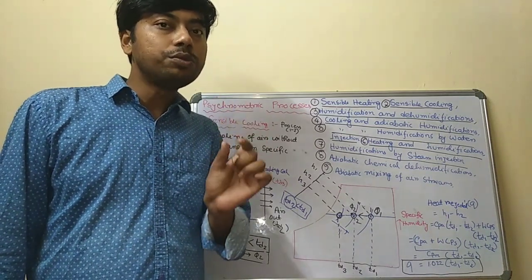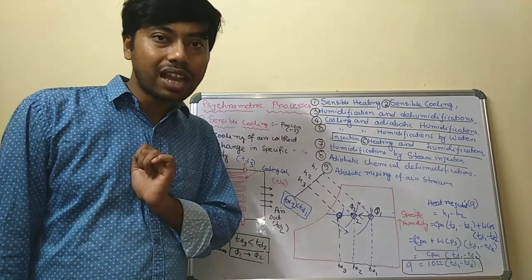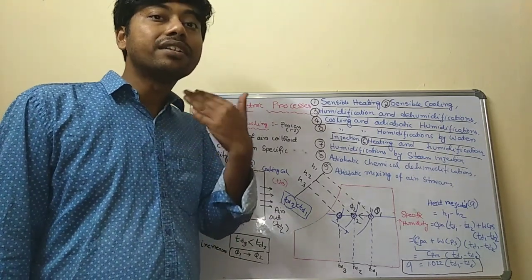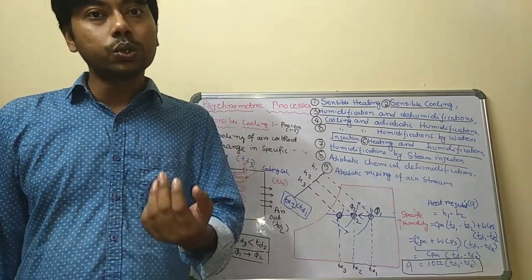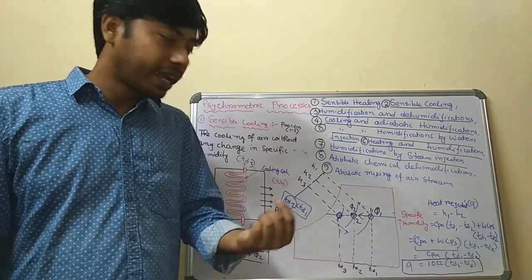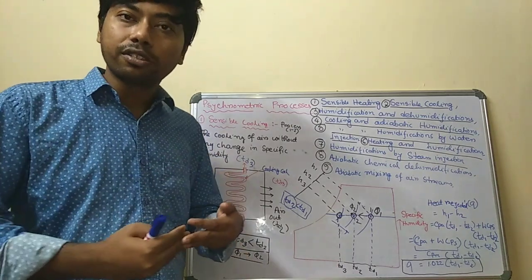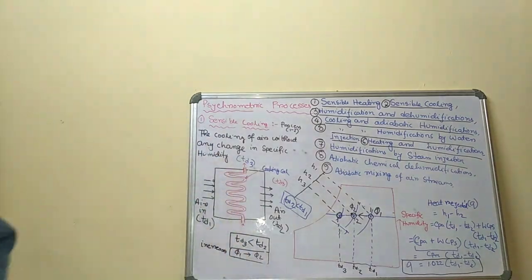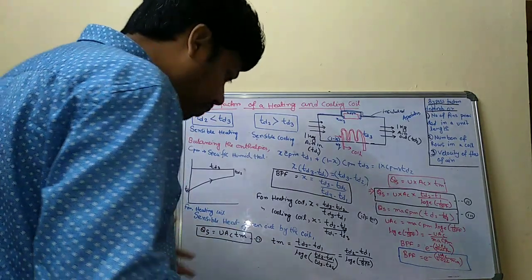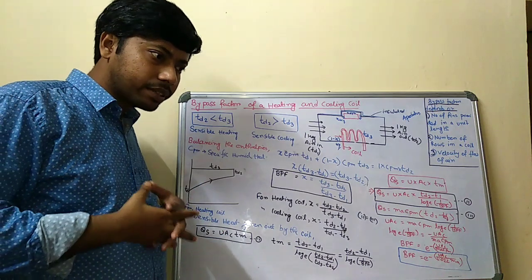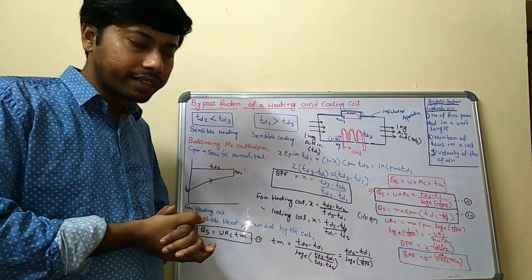Now, the specific humid heat value is basically 1.022. We already discussed that. So the total heat rejected during the sensible cooling process will be 1.022 into TD1 minus TD2. Okay, so this is the sensible cooling process. As we discussed, what is sensible heating and what is sensible cooling, and what processes take place in sensible heating and sensible cooling.